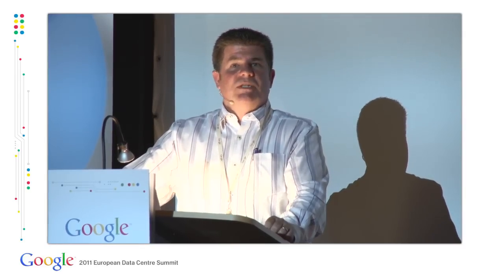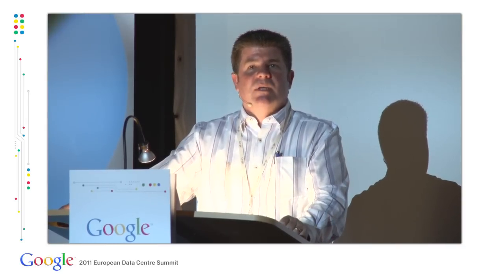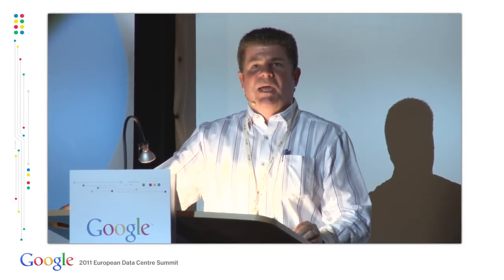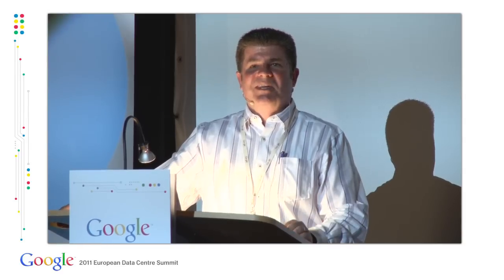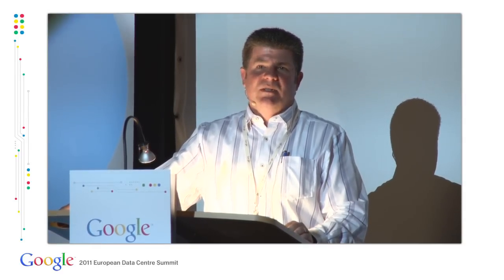Yeah. So if you don't have it in house, we believe that it's a really important component because you need to be validating what you're doing all along the way. And then you mentioned that you just started doing things. So did you start to do some of your step 1, 2, and 3 before the initial CFD was complete, or did you run a CFD and then have at least basic results to go on? So the initial things that we just knew were wrong right off the bat, we just did. And then we went in and did the modeling to verify where we were at before we took any of the more aggressive steps. When you take a data center professional into a room, they just know that your perf tile distribution is wrong based on where the heat load is. Those are things that you can just do without really having to model first, right?